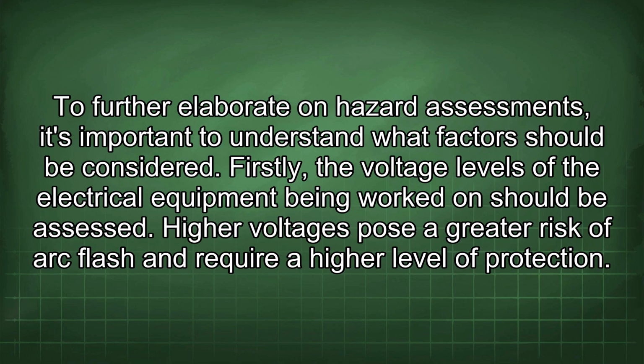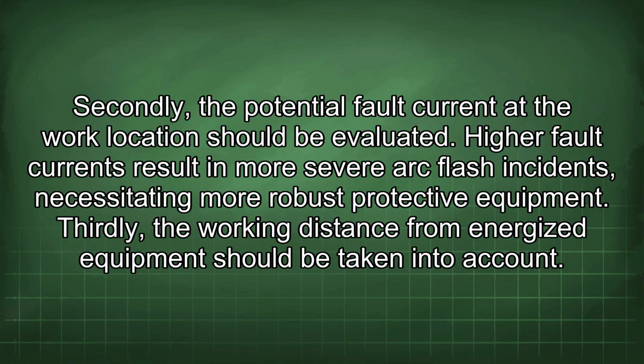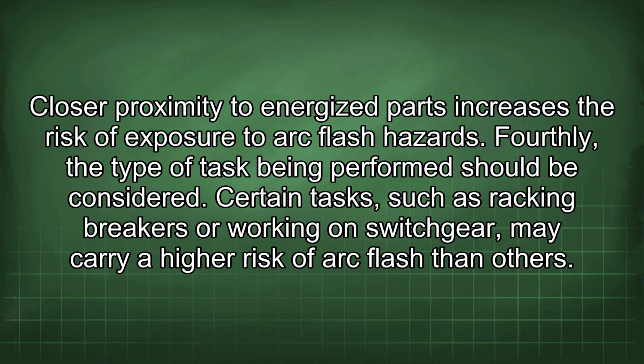To further elaborate on hazard assessments, it's important to understand what factors should be considered. Firstly, the voltage levels of the electrical equipment being worked on should be assessed. Higher voltages pose a greater risk of arc flash and require a higher level of protection. Secondly, the potential fault current at the work location should be evaluated. Higher fault currents result in more severe arc flash incidents, necessitating more robust protective equipment. Thirdly, the working distance from energized equipment should be taken into account. Closer proximity to energized parts increases the risk of exposure to arc flash hazards.